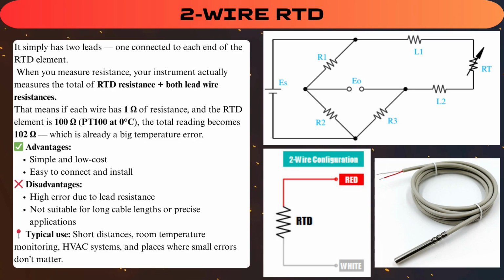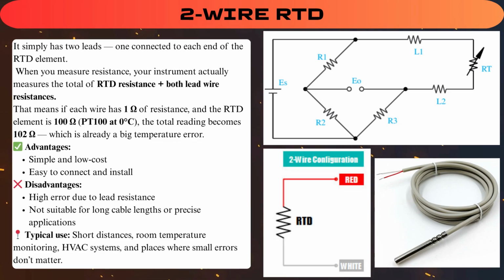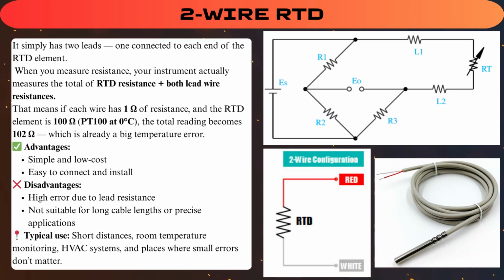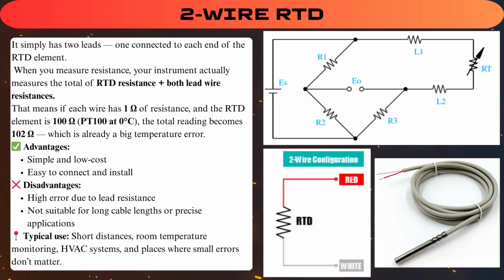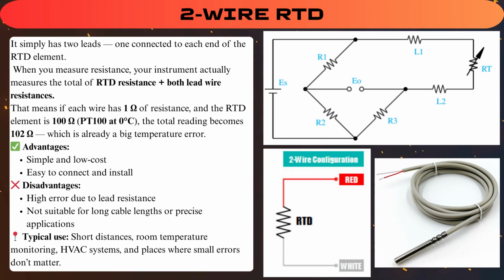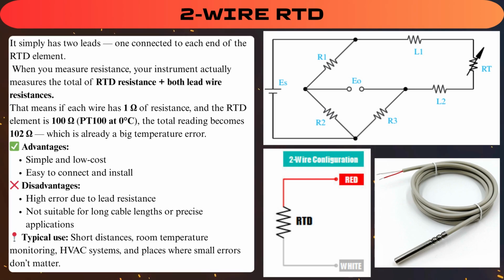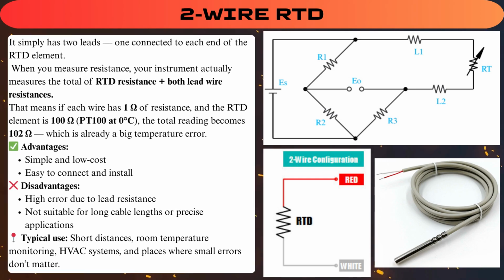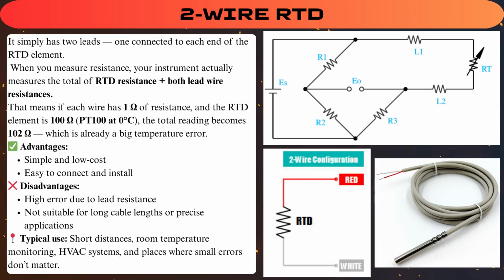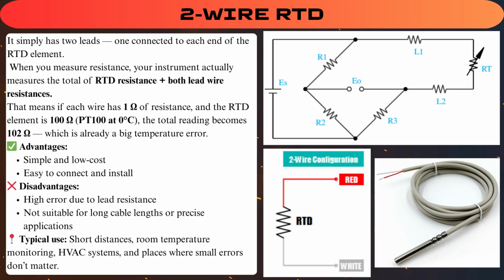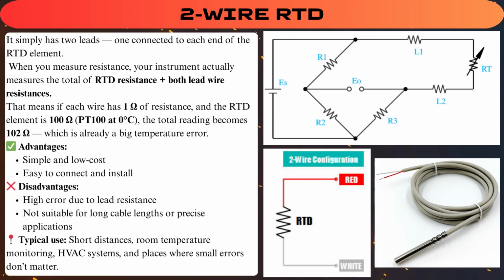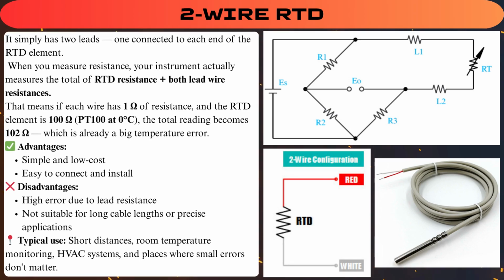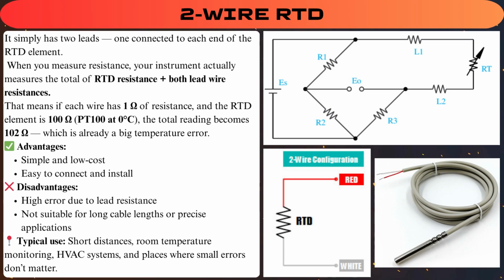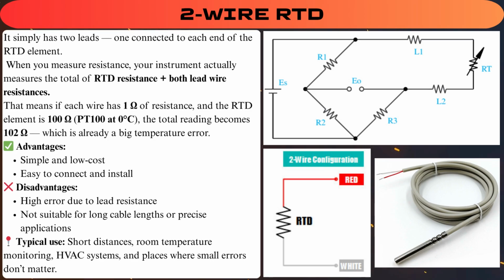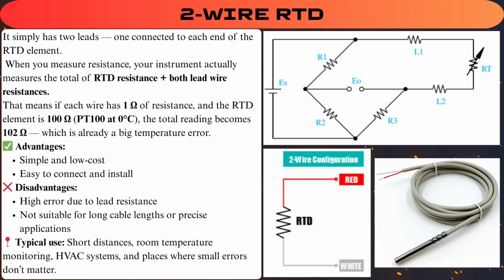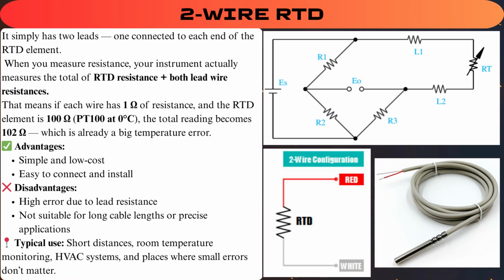It simply has two leads, one connected to each end of the RTD element. When you measure resistance, your instrument actually measures the total of RTD resistance plus both lead wire resistances. That means if each wire has 1 ohm of resistance and the RTD element is 100 ohms, PT100 at 0 degrees Celsius, the total reading becomes 102 ohms, which is already a big temperature error.